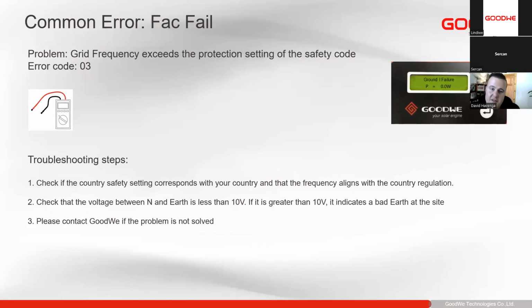The next one we have is Fac Fail, which is similar to the VAC failure, except it's the frequency. So just make sure that you have selected the correct country code, because typically the frequency is not a big problem in most countries. Voltage is more a problem than frequency. So just check the voltage between neutral and earth, and if the frequency is correct and everything and you're still having it, then you can contact us for further support.